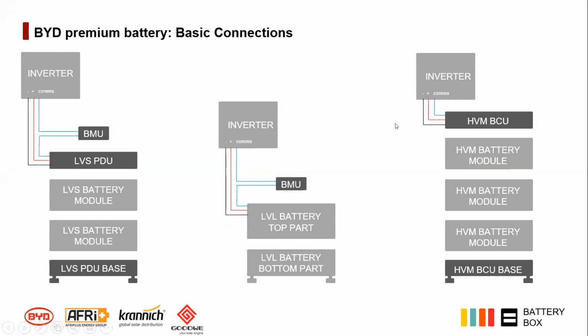And then on our right, we have the HVM batteries. If you're installing an HVM, you start with the HVM base, and you make sure the base is flat. You put your battery modules on top of each other. You can have between 3 and 8 battery modules per tower, and each battery is 2.7 kilowatts. Then on top, you'd have your HVM BCU. Your power connections to your inverter would be connected in your HVM BCU, and you wouldn't require an external BMU. Your communications to the inverter connect directly to your BCU. The LVL is also a little bit stackable, so you can put one LVL on top of another. So you have basically a 30 kilowatt tower of low voltage batteries.